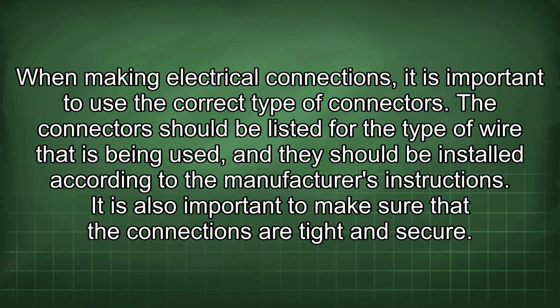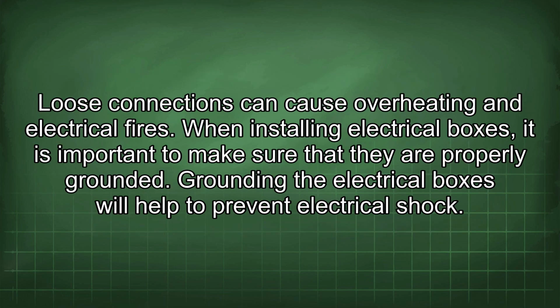When making electrical connections, it is important to use the correct type of connectors. The connectors should be listed for the type of wire that is being used, and they should be installed according to the manufacturer's instructions. It is also important to make sure that the connections are tight and secure. Loose connections can cause overheating and electrical fires.